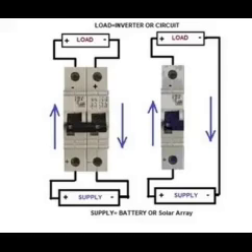When you are using your MCB for a DC application, of course that MCB will be a DC MCB. There also you will find connections marked positive, negative, and supply and load. In case you reverse this connection or make a mistake in connecting the MCB over line and load, it may catch fire when the overcurrent or short circuit protection is triggered.